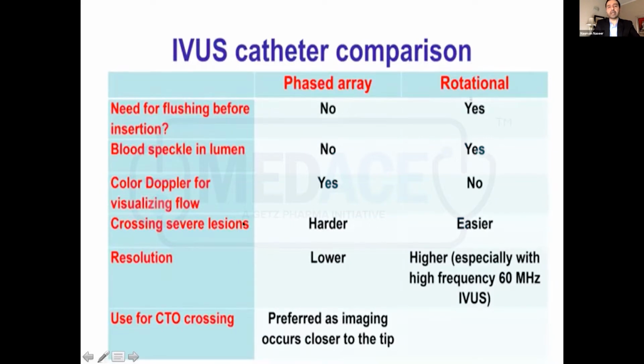The phased array catheter is a little bit bulkier, so it might be harder to cross more severe lesions than the rotational catheter. The resolution is generally 20 megahertz with these phased array catheters, but it can be much higher, 40 and 45 megahertz, and now up to 60 megahertz with the more recent rotational catheters. For CTO crossing, phased array catheters are preferred because the imaging is closer to the tip.